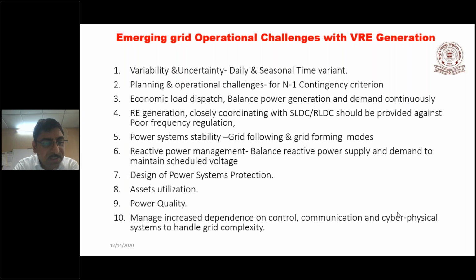Then there's another point, the design of power system protection. Dear friends, whenever there's any fault in the system, you have to clear the fault. Faults can be cleared with the help of relays, there's no doubt, but those relays only work on the principle of current and voltage. Whenever any fault happens, there's a drastic change in the current of the system. Current goes up manifold, like 4 times, 6 times, 7 times or 8 times, depending upon the short circuit strength of the system. And the voltage drops to 50%, 30%, 20%, and even close to zero if it's a dead short circuit fault.